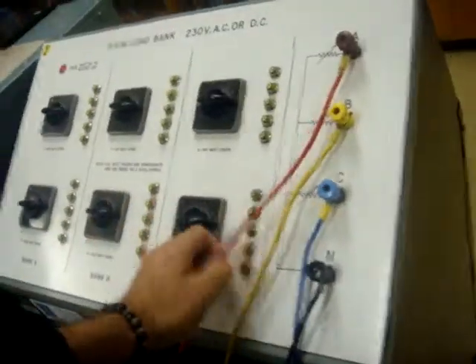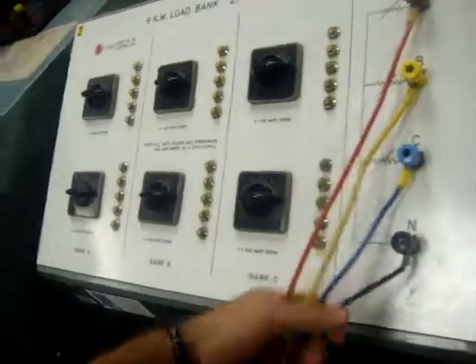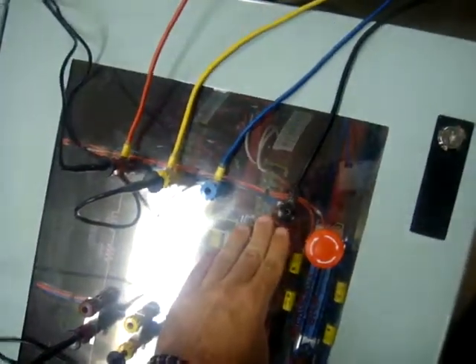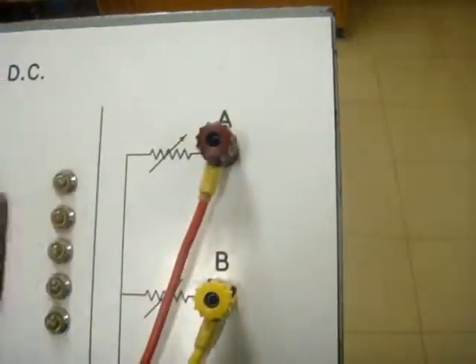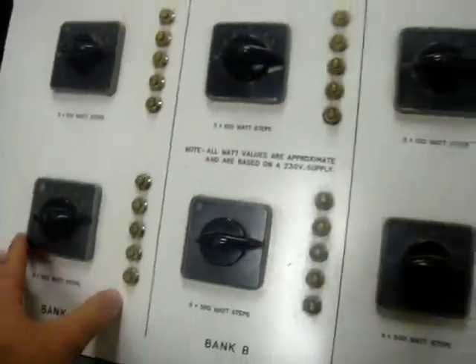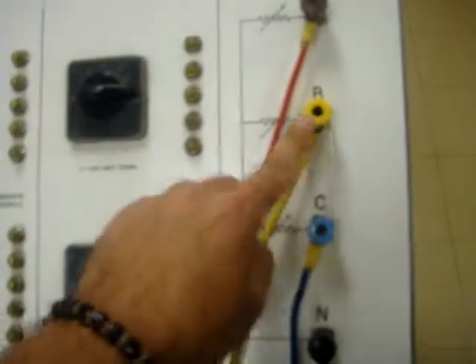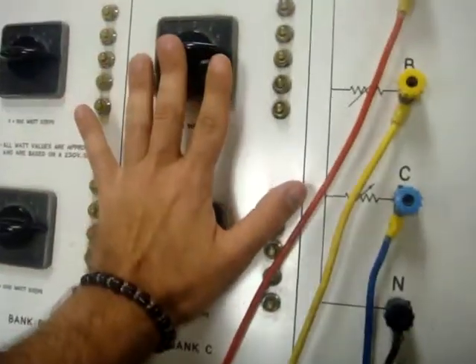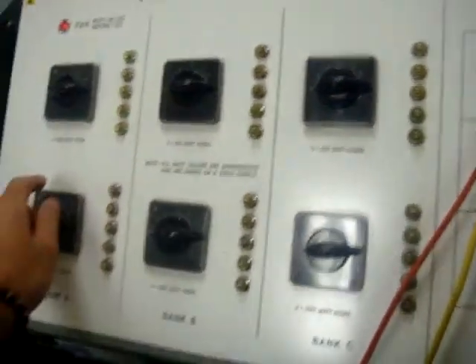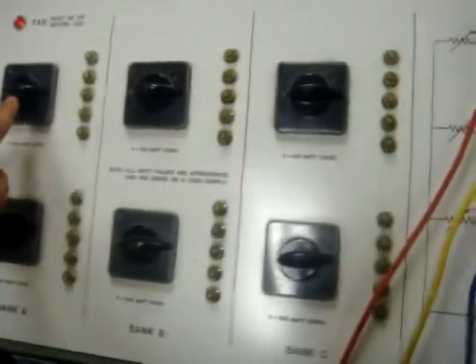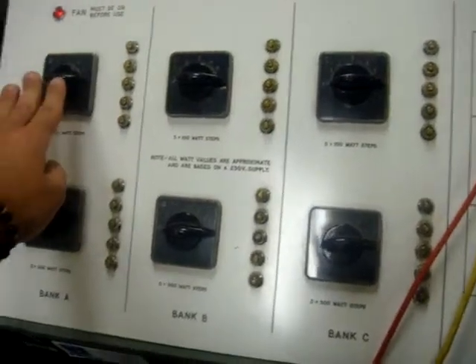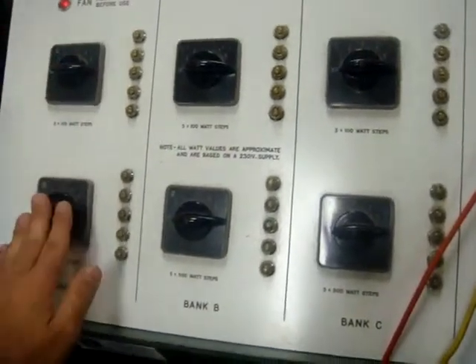This load bank connects a red, yellow, blue and black wire directly to the receiving end terminals of the artificial transmission line. Besides that, the red terminal here corresponds to bank A, the yellow terminal corresponds to bank B, and the blue terminal corresponds to bank C. Each of these banks have an increase of either 100 watt or 500 watt steps.